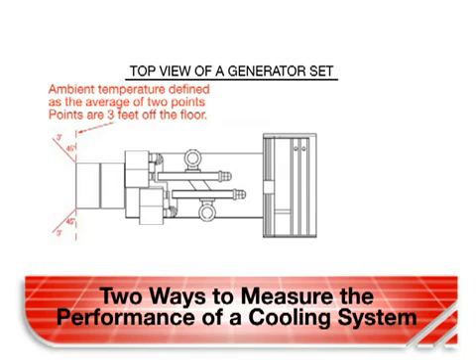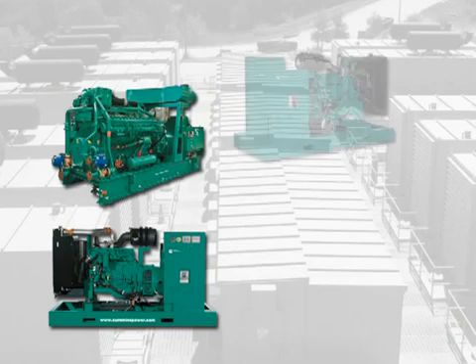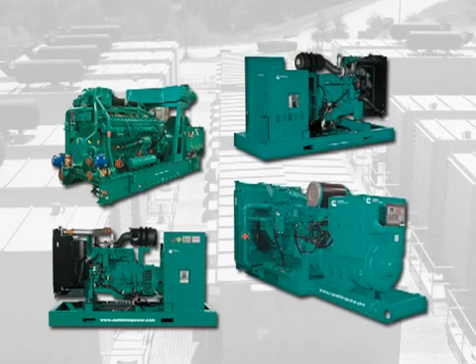This temperature is typically measured as an average of two points, as shown in the diagram. In the case of enclosed generator sets, the temperature is typically measured at the air inlet louver. The AOC temperature, on the other hand, is measured on the face of the radiator. The air flowing through the radiator is significantly warmer than the air entering the system, so AOC temperatures are higher than corresponding ambient ones.